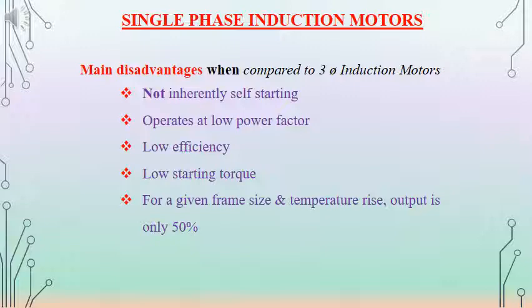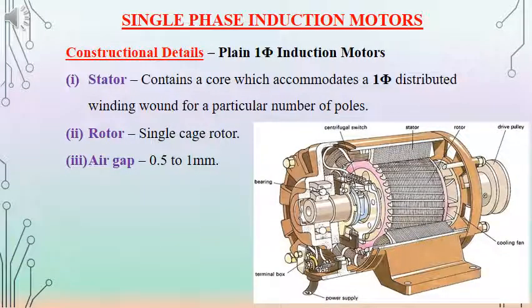The starting torque is very low in the case of single phase induction motor when compared with three phase induction motor. For the same frame size and temperature rise, the output is only around 50 percent in the case of single phase induction motor compared to three phase induction motor.